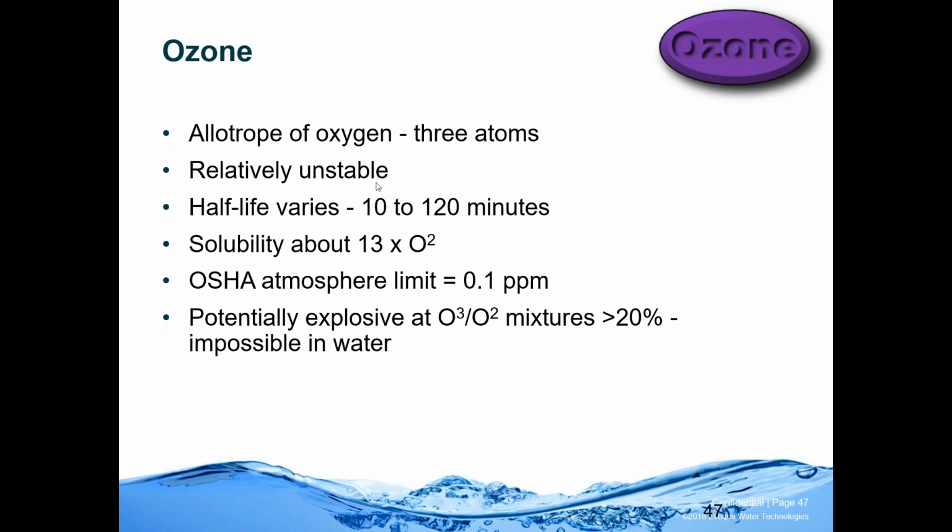Ozone, or O3, is a very powerful oxidizing agent. The OSHA limit is put here because this is a safety concern. OSHA does limit it to 0.1 ppm, an 8-hour weighted average, and it's not difficult to comply with that. There normally should not be any ozone in the room atmosphere when everything is working properly. You could have an explosive ozone mixture, but in water, it just can't happen.